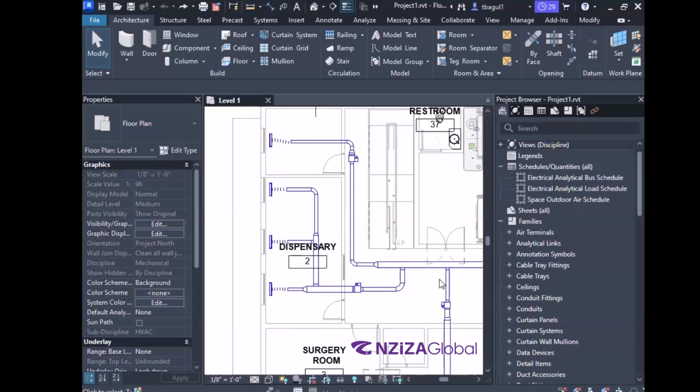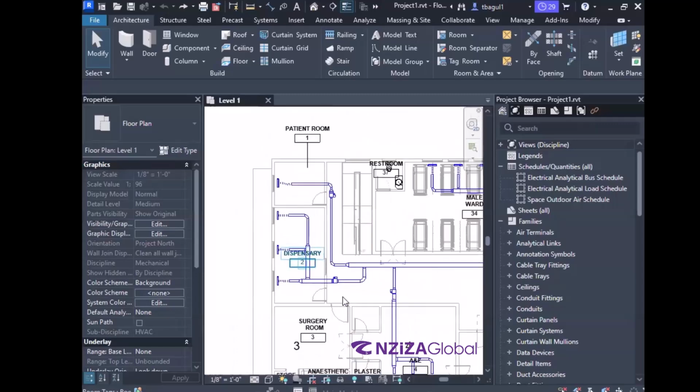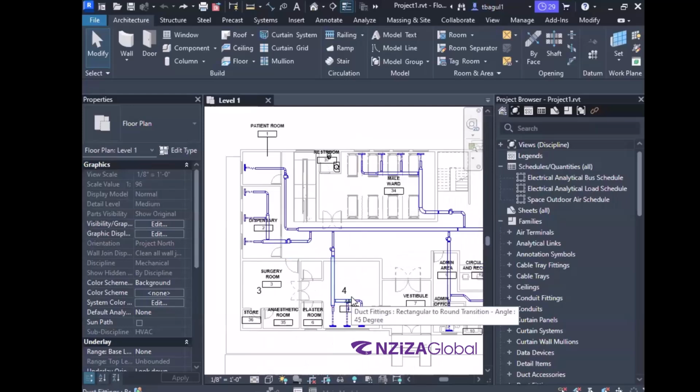Again, I would strongly urge everyone to do the heat load calculation one by one. This is a very important thing. We have given enough priority to it. Make sure that it happens. All right. And again, go through room by room. I know there was a brainstorming over here where we mentioned, do we need to do this one by one? Is there a rule of thumb for doing this? A rule of thumb will work okay if you are working on a hospital, an office project, maybe a hotel project. Over here, it becomes very critical to make sure that we have the proper concepts applied.